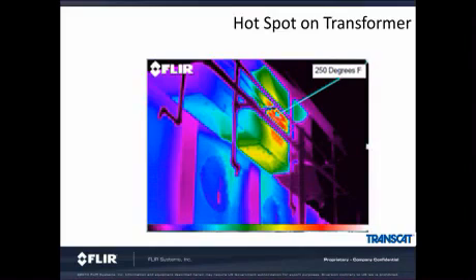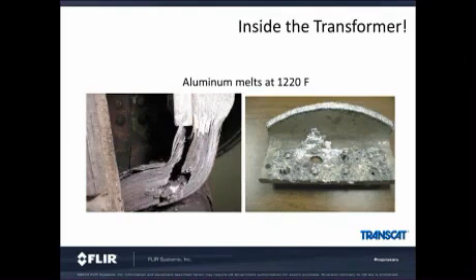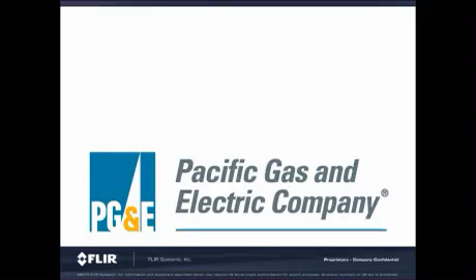Here we will discuss another example of indirect temperature measurement. Using the thermal camera, the customer was able to find a 250-degree isolated temperature rise on the side of a transformer. After discovery, a repair was initiated, and this was found. The component was made out of aluminum, and you can see it was falling apart and melting. Aluminum melts at 1220 degrees Fahrenheit, so you can imagine how hot it actually was. This temperature rise was approximately 6 times greater than what was seen on the outside of the compartment. This could have been a catastrophic problem if it went undiscovered.